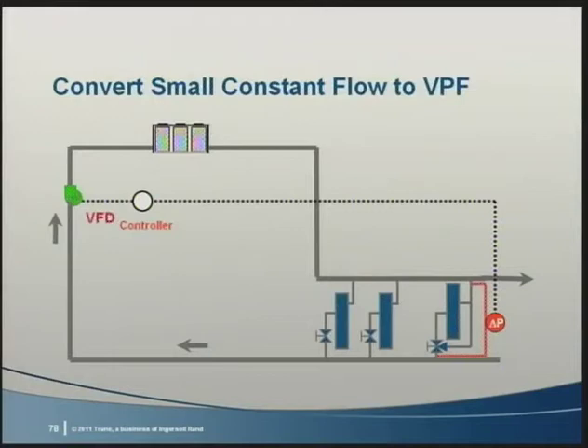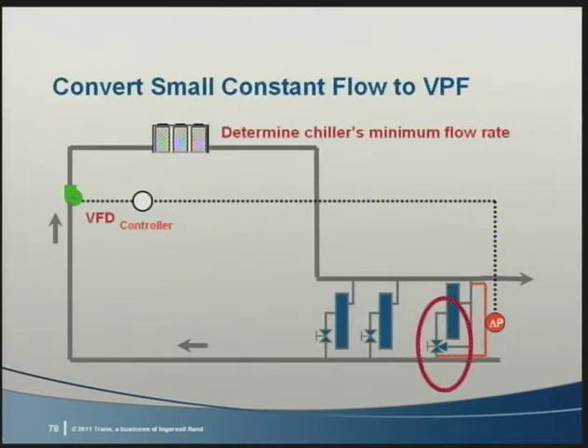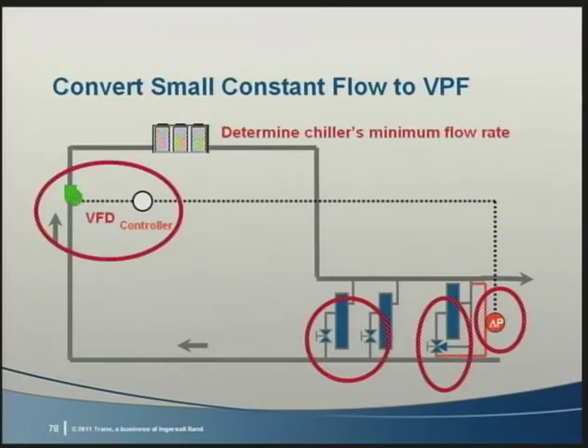Will do. We'll start small and move up. In a small single chiller system, if the chiller controls allow variable flow, a retrofit from a constant to variable flow system may be simple. First, determine the chiller's minimum flow requirements. Next, find 3-way valves that, when their flow is summed, allow the chiller minimum flow rate to be met. It would be best if they were hydronically the furthest from the pump. Put a differential pressure sensor at the most remote air handler that has a 3-way valve. Now, to make the system variable flow, convert the rest of the 3-way valves to 2-way valves. Finally, put a drive on the pump and control it to maintain the system differential pressure set point.